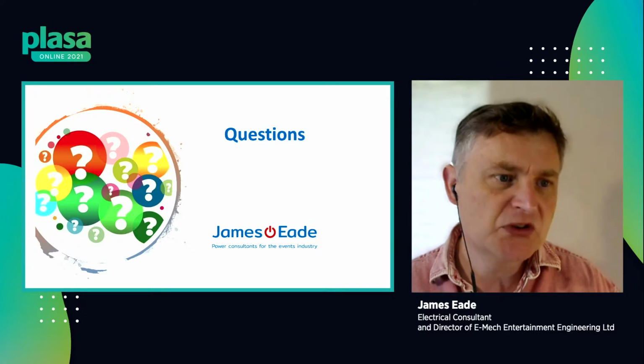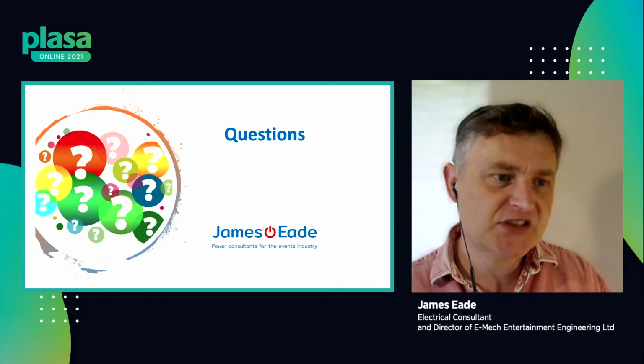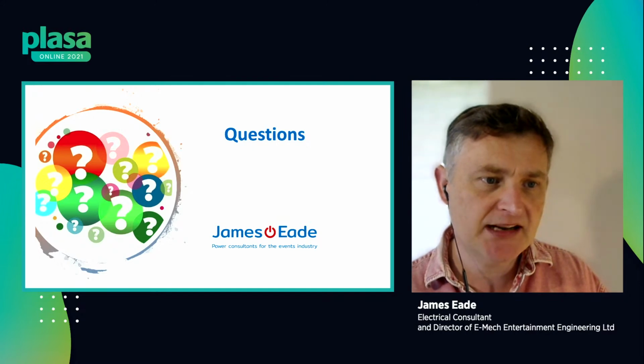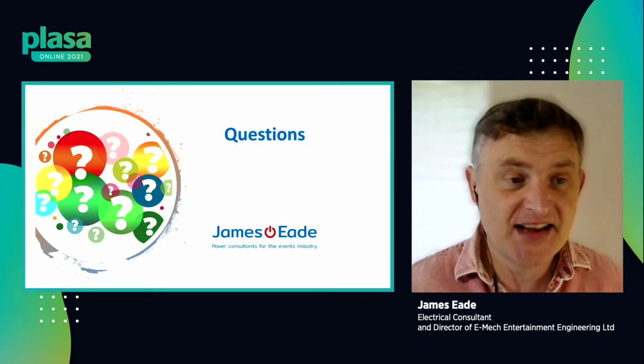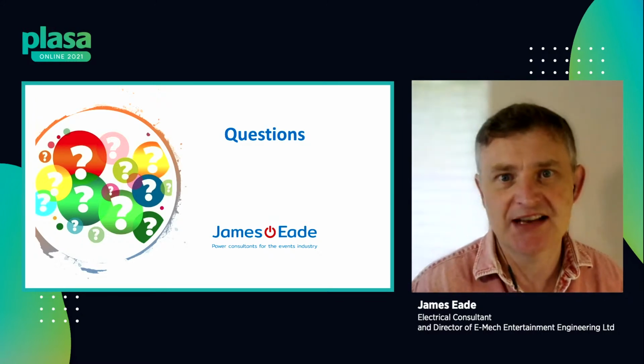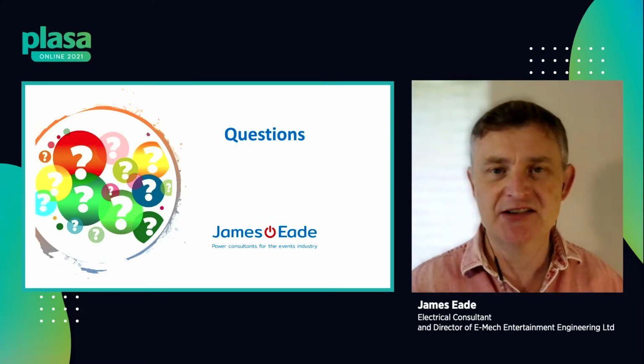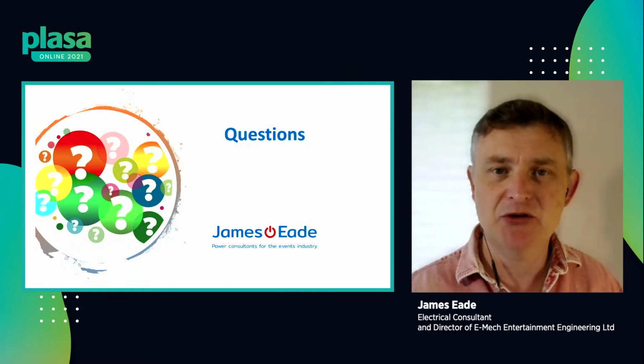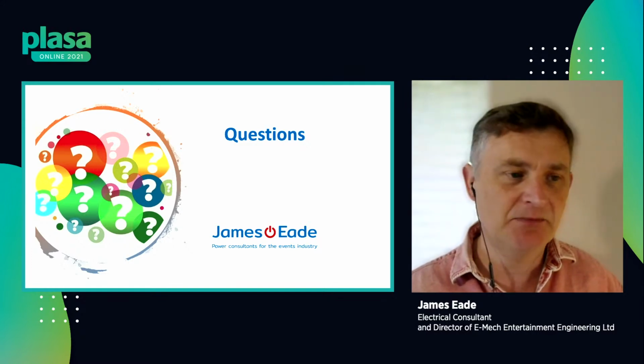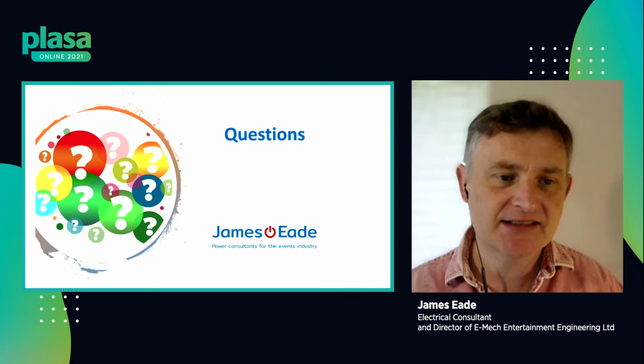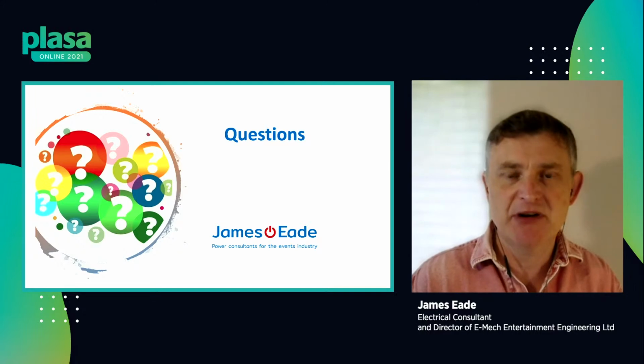Anonymous asks, what's the best way to calculate total load? So you've got a three-phase 63 amp supply - how many dimmers can you connect, assuming they wouldn't be at full? It's difficult to say. You've just got to toss up how many lights you've got in the lighting rig, work out how many you'll have on at any one time, and add that up. You can allow a bit of diversity. That's the only real way you can do it.